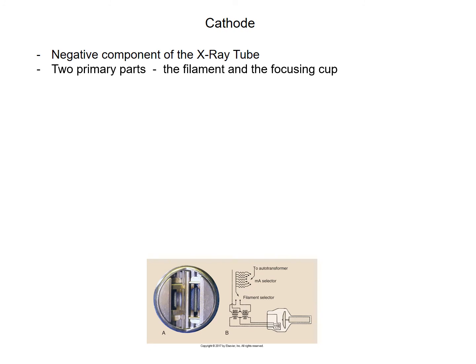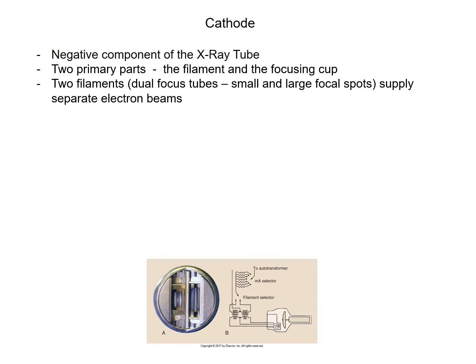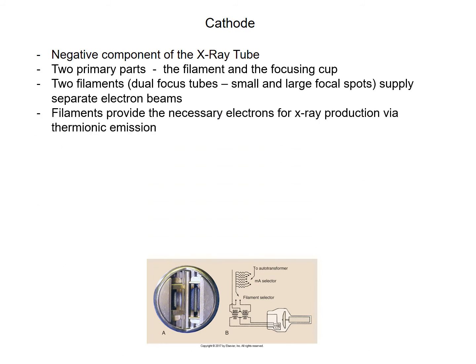Two primary parts of the cathode. You've got the filament and you've got the focusing cup. Two filaments, we call this dual focus tubes, supply separate electron beams. The filaments provide the necessary electrons for X-ray production via thermionic emission. Remember, when we heat up the filament, we're starting to boil off electrons from the filament, and those are the electrons that are going to then stream across the gap between the cathode and the anode. We call this the tube current. Those are the electrons that are going to bombard the anode to create X-rays.